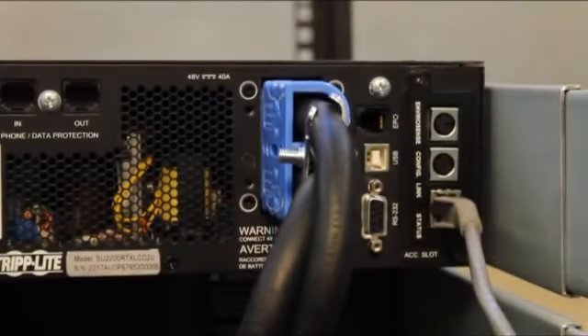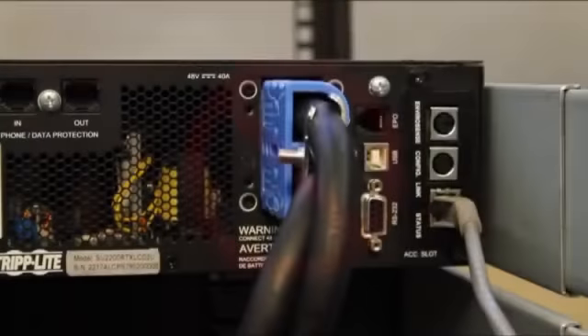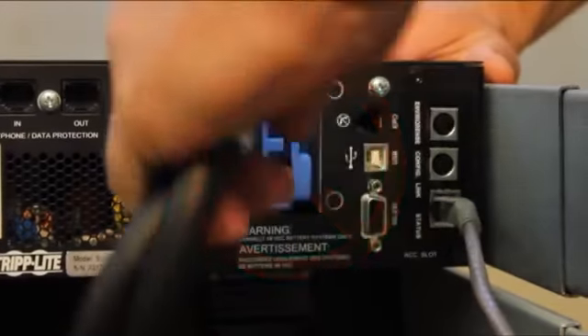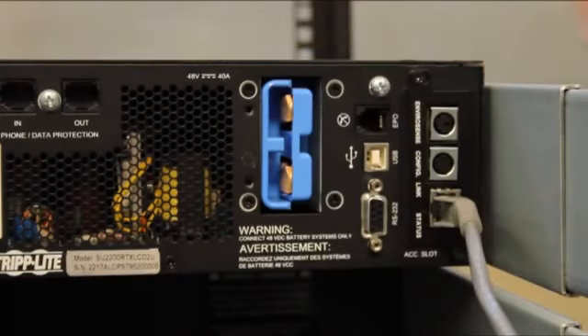Connect the battery module to the power module. Small sparks may result during this connection. This is normal. Do not connect or disconnect battery modules when the UPS is running on battery power. Select models feature a battery charge level switch located just below the external battery connector.